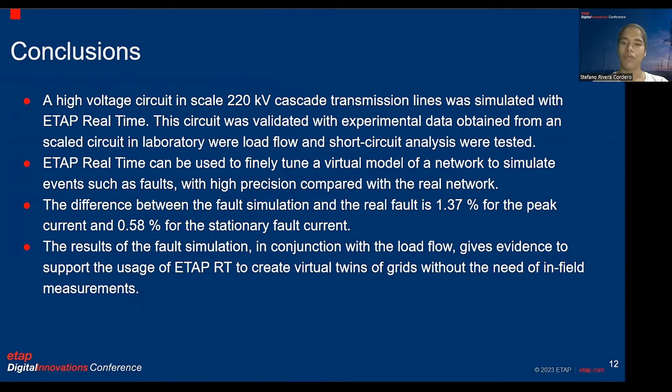The difference between the fault simulation and the real fault is 1.37% for the peak current and 0.58% for the stationary fault current. The results of the fault simulation in conjunction with the load flow gives evidence to support the usage of ETAP Real-Time to create virtual twins of grids without the need of in-field measurements.